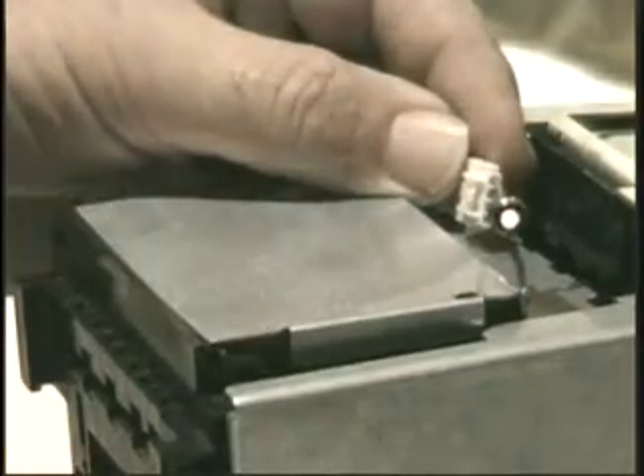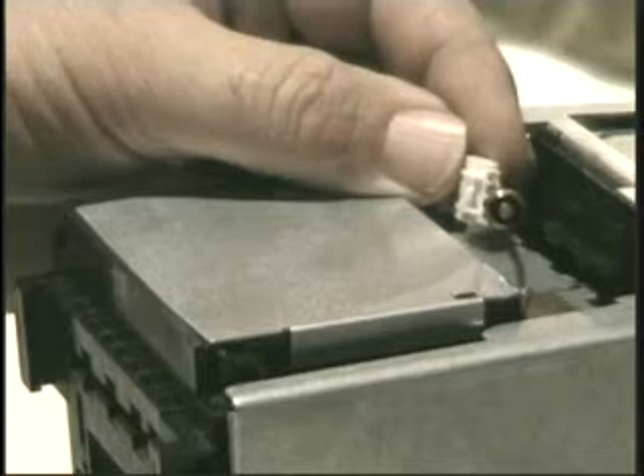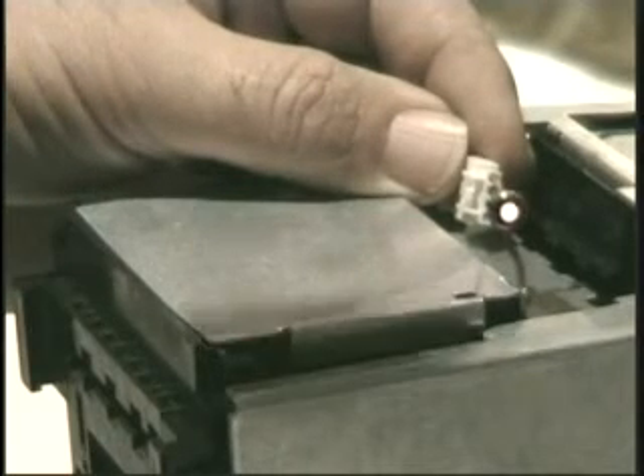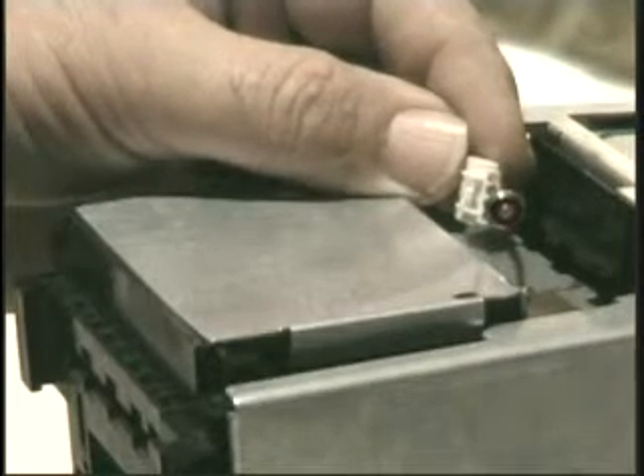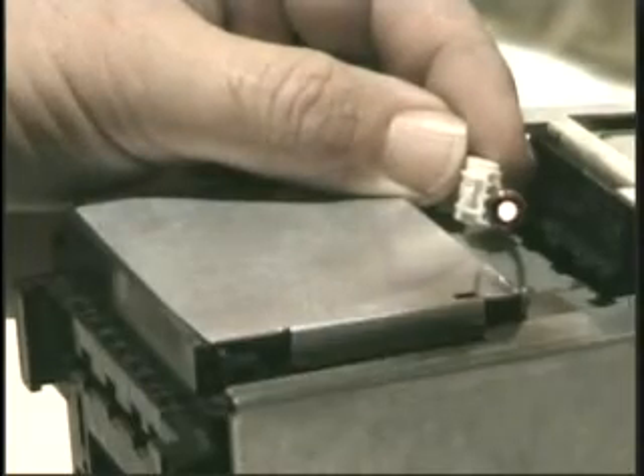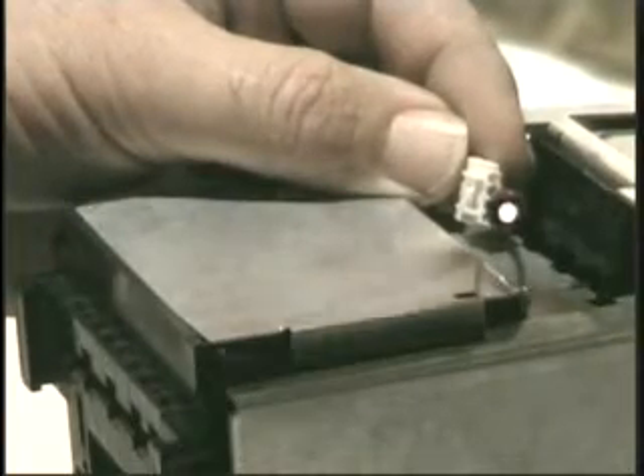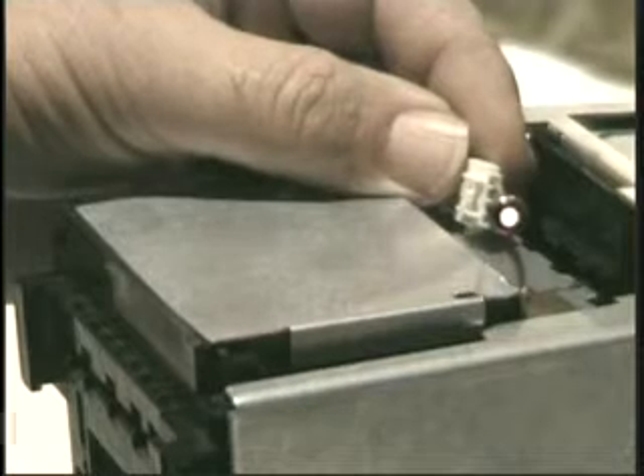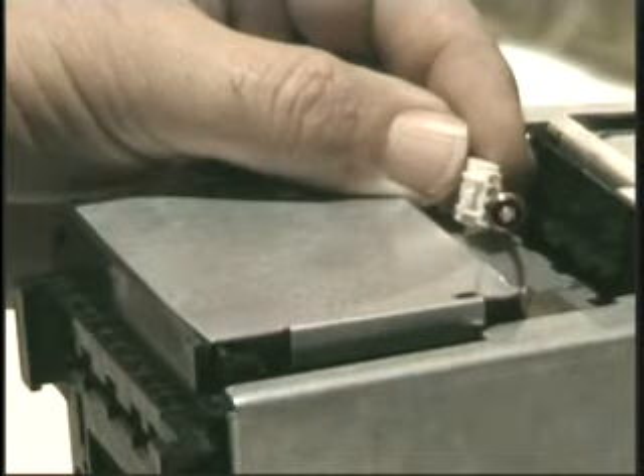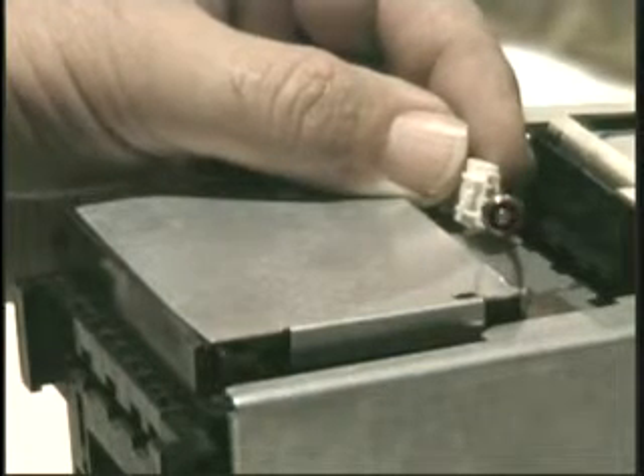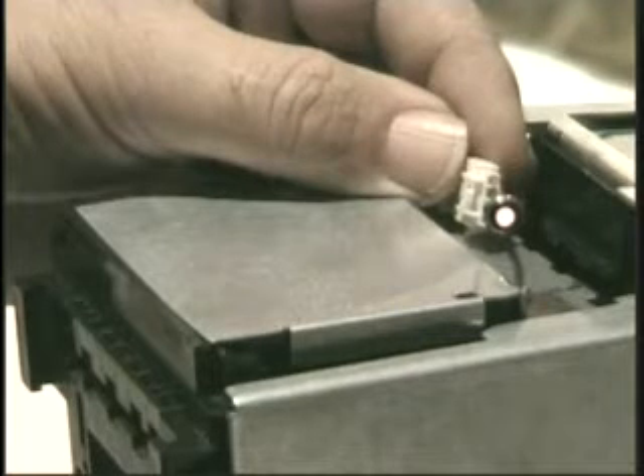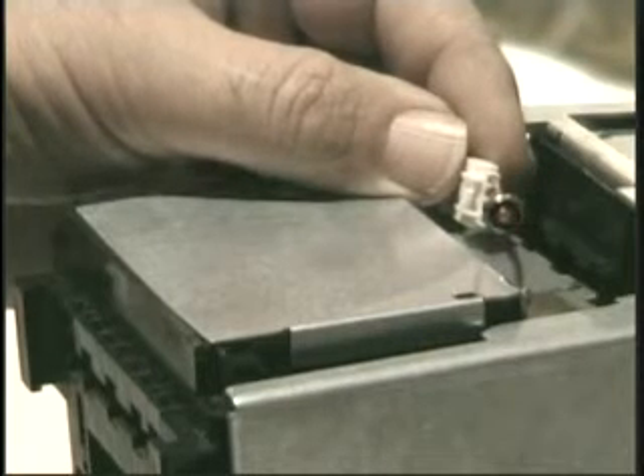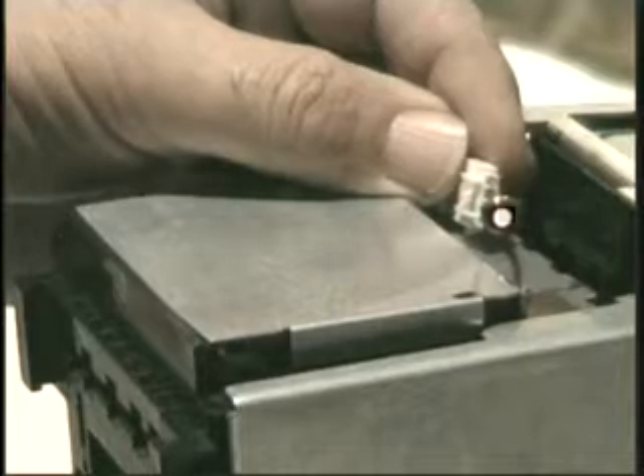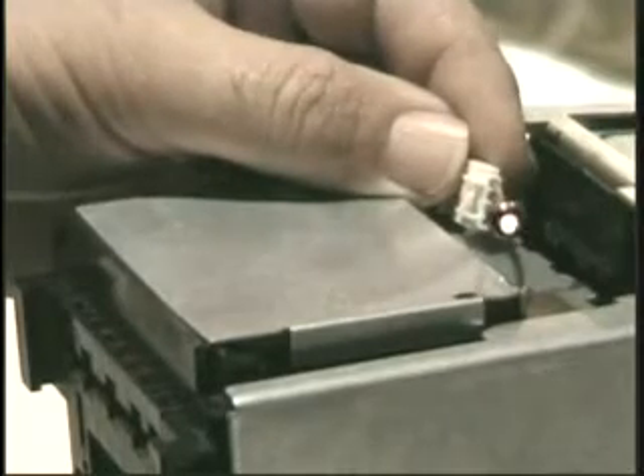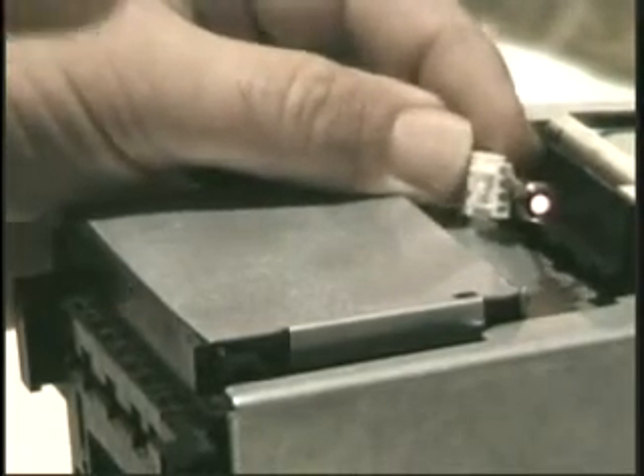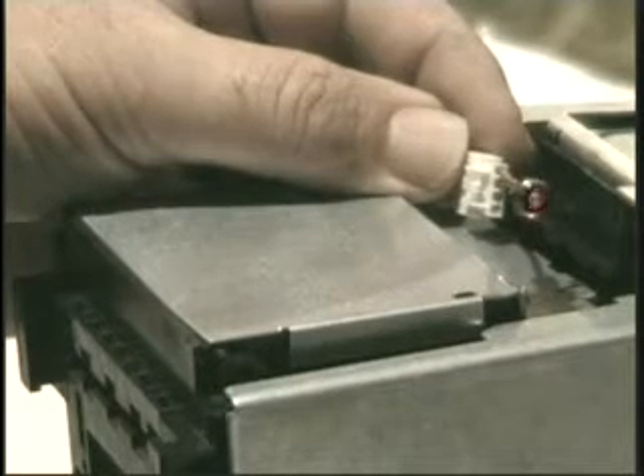When you're doing sensor tests, especially on the transport, get this out of the frame. While testing, wiggle the wire harnesses. A lot of times it's not the optic and it's not the plug, it could just be a wire with a bad connection at one of the connectors. Wiggle the harnesses while testing the sensor, it could be a bad connection there. But it's pretty easy to diagnose with this. Using test 8 or test 4 gives you an error code, take that code to the chart, now you know what sensors to test, and troubleshoot down to whether it's the optic or the wire.